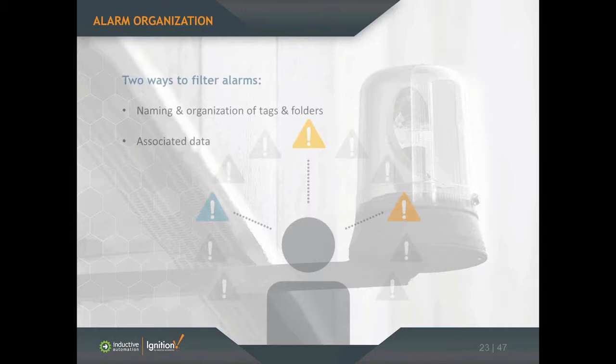The first way is through the naming and organization of tags and folders. For example, you may have two different areas of your plant, Area A and Area B. If you organize your alarms in those two folders, you have the ability to filter on those particular areas.